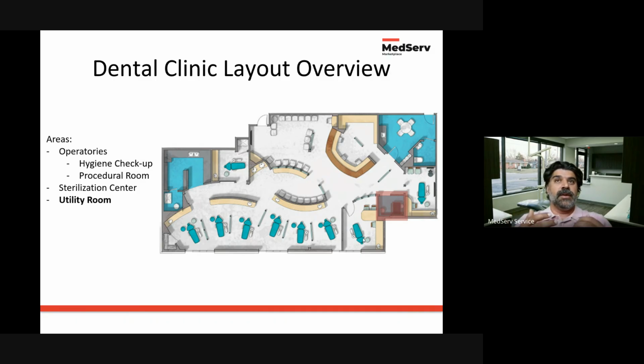Typically, they install the equipment, they close the door, and then they turn the switches to power on and off from outside the room, and they rarely ever look inside there to see what's going on or check on it too. So, like some of the issues I was mentioning earlier, if it's a weak handpiece, it typically has something to do with the compressor. If you have poor suction from your HVE, that also can be a restriction or cloggage in the vacuum. If you have water coming out through the airline, through the air syringe, that means that your air dryer function is not working.